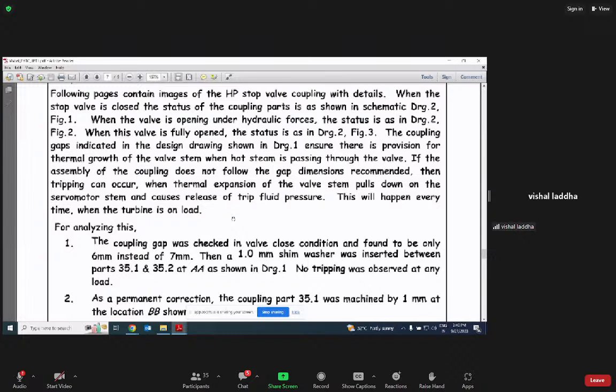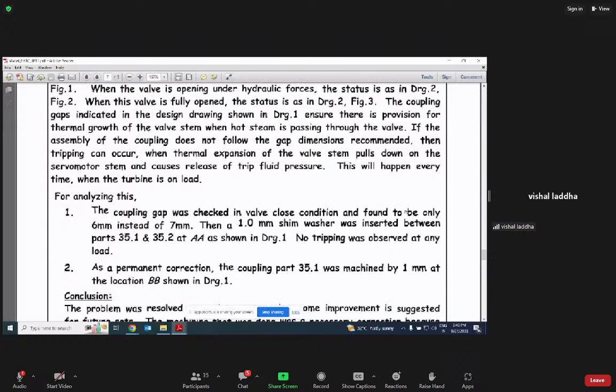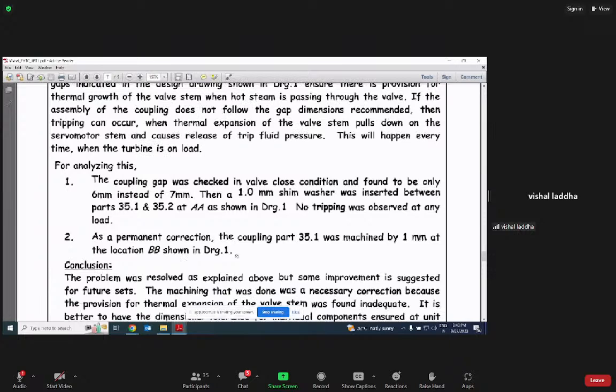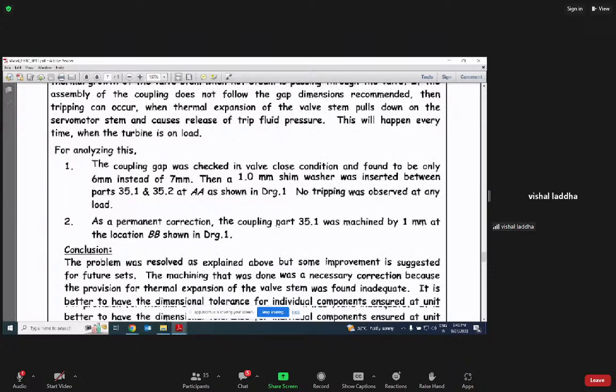So for analyzing this, the coupling gap was checked in the closed condition and found to be only 6 mm instead of 7 mm. Then a 1 mm shim washer was inserted between parts 35.1 and 35.2 in drawing 1, and no tripping was observed. As a permanent correction, the coupling part was machined by 1 mm at the location BB.